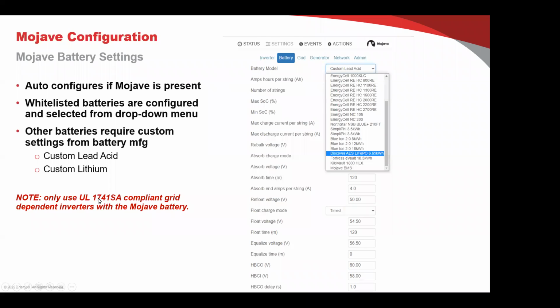Then to configure it, you click on settings, select battery, click over here on the drop-down menu, and then pick a battery. Okay, so it's our battery, it's Mojave. I don't believe we're going to start selling the battery and the inverter separately until later, what, May, June timeframe? Right around there, yes. But in the beginning, we're just selling them as ESS packages. So you come in, you select Mojave, but if you opted for a different battery system in the future and it's a whitelisted battery, you select it from a drop-down and then all the battery settings are done. If your battery's not on this list, then you do a custom lead acid or custom lithium and then put the settings in as you need.